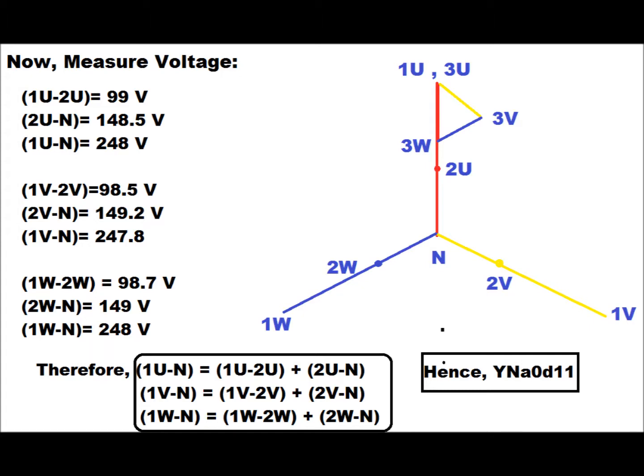We can conclude that the measured voltage between primary red-to-neutral, primary yellow-to-neutral, and primary blue-to-neutral is equal to the sum of the primary-to-secondary voltage plus secondary-to-neutral voltage for each respective phase. Hence, combining all these conditions, it is confirmed that the vector group is YNA0D11.